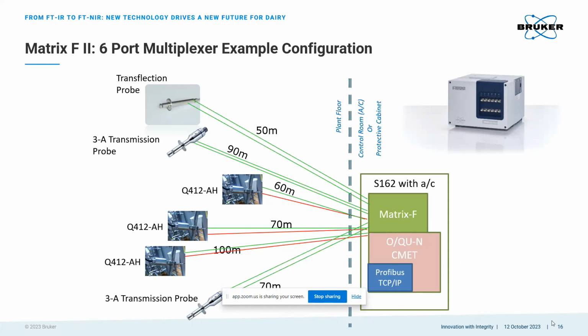So here we have an example of a 6-port multiplexer system. The Matrix F2 can be connected to different types of probes with different fiber lengths. So this makes the system completely configurable to your needs, where you're not having to pay for more than what you need. And again, by utilizing only one spectrometer, your cost per analysis goes way down, such that in most cases, this makes it possible to get an ROI within 3 to 6 months after implementation.